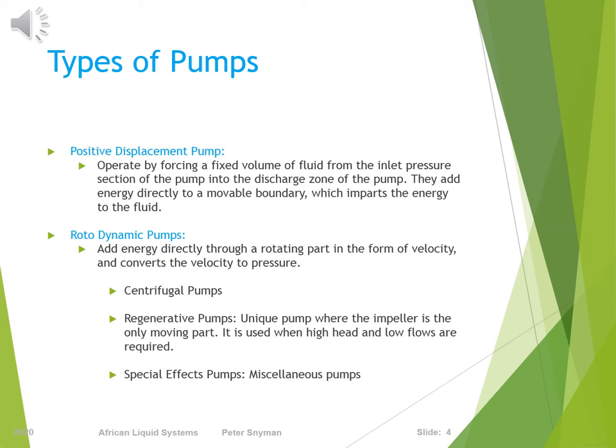Positive displacement pumps are essentially rotary or reciprocating machines, in which energy is periodically added by application of force to a movable boundary of fluid enclosed in a chamber or pipe, which results in a direct increase in pressure. Roto dynamic pumps are essentially rotary machines, in which energy is continuously imparted to the pump liquid by a rotating part, such as an impeller or a propeller.